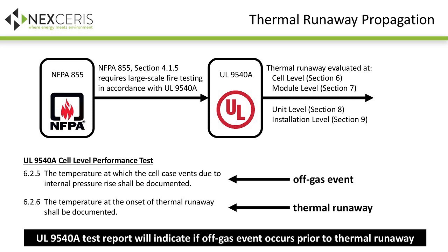standard, or test method, I should say, goes through a series of tests where they evaluate cell failure at the cell level, the module level, and so on. One of the areas to look at is within the cell level performance test. There are two specific and discrete data sets that are collected. They're looking at the temperature at the surface of the cell. Under a cell abuse test, they're looking at the temperature of the cell when the cell vents, and there's a specific definition of venting, and also the temperature of the cell when it goes into thermal runaway.